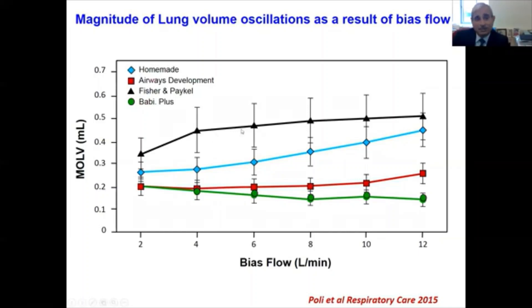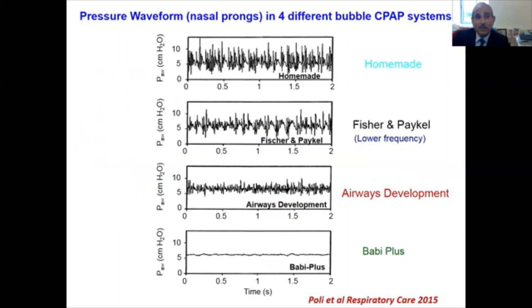In contrast, with the Babi Plus system at flows higher than 4 L/min, there was a decrease in oscillation. One reason is that the Airways Development and Babi Plus systems utilize a diffuser in their bottle, and that diffuser attenuates the oscillations and decreases the interaction between air and water. From this data, the Fisher & Paykel and homemade systems perform much better. Additionally, at flow rates over 8 liters per minute, the homemade and Fisher & Paykel systems generate second bandwidth frequencies at 54–76 Hz and 61–71 Hz respectively, which may promote enhanced lung recruitment.